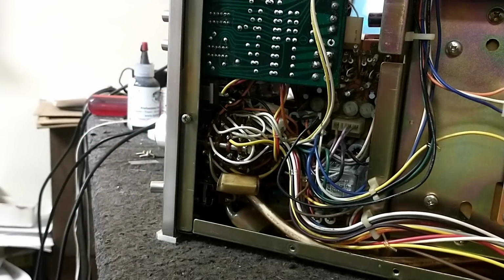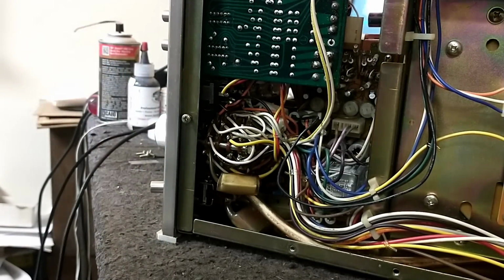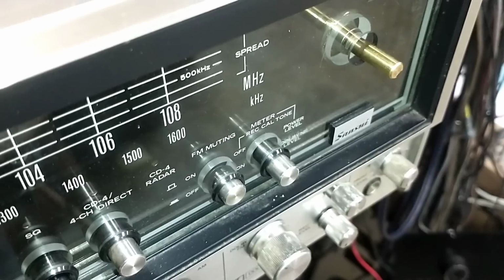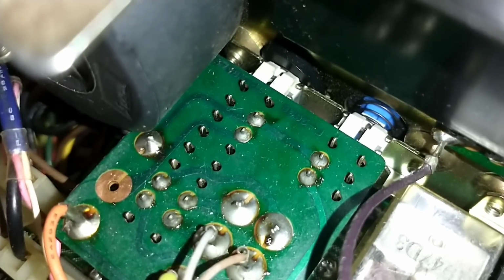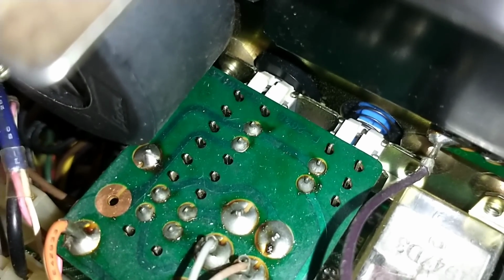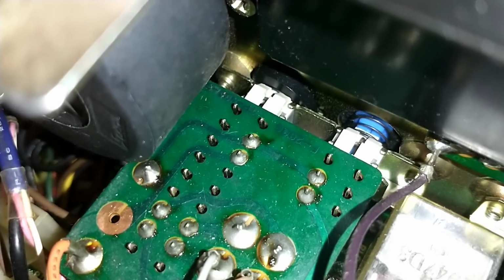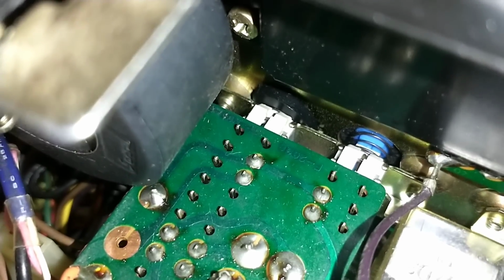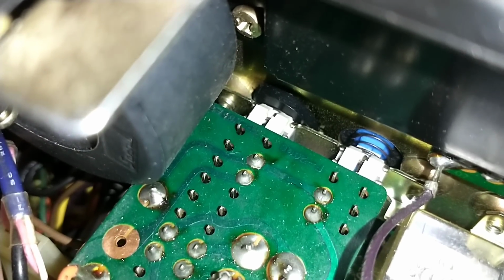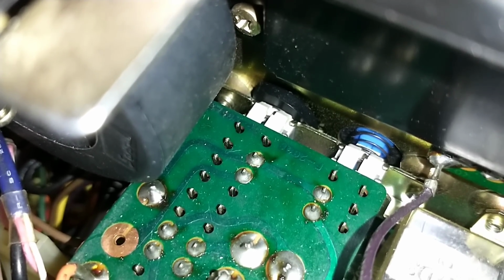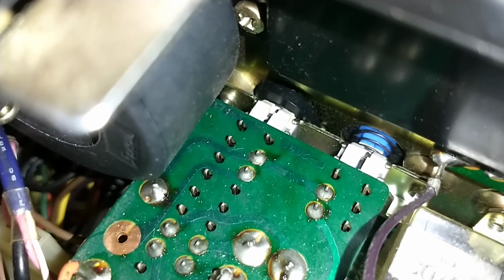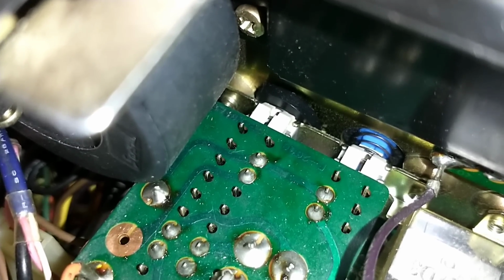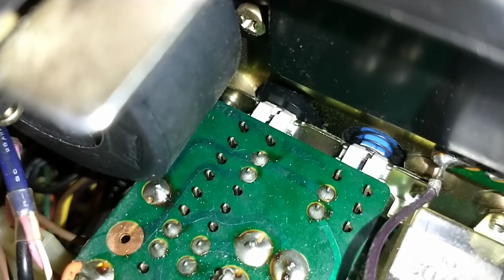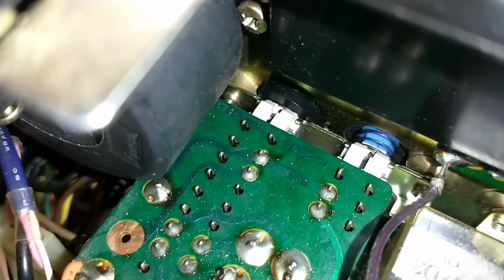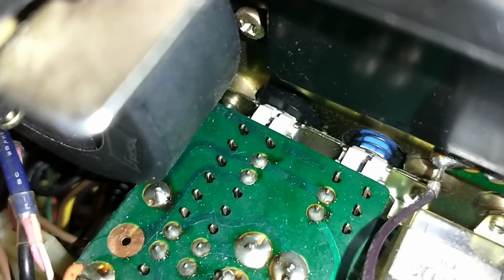Alright, just so that's clean. Now let's go ahead and move to the meter control switch up top. So this is a little trickier to get to, but your goal is you don't have to remove the circuit board. What you do is you get the cleaner down into the latch holes there. That's the center gap on the white thing. If you get your contact cleaner in there, capillary action will suck it in, and then you can work the switch and clean it up. But that's really all you need to do here to clean that.